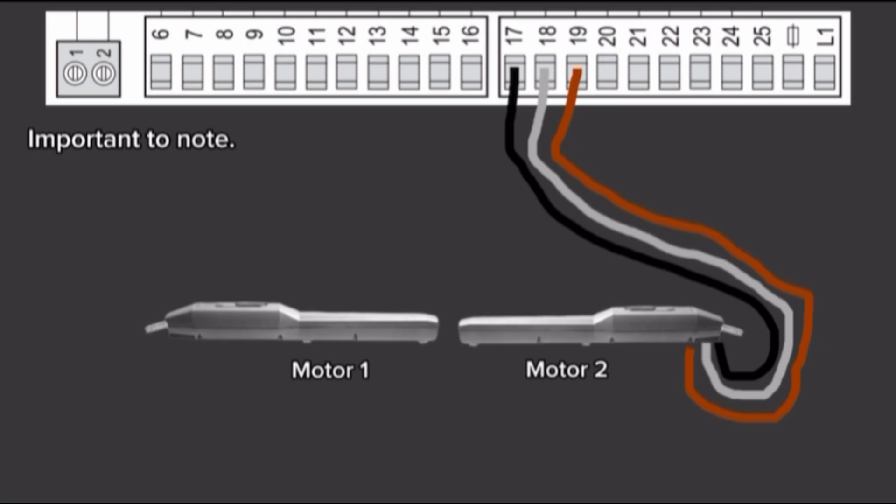Important to Note. Capacitor always connects between phase wires. Don't connect with motor common. Let's connect Capacitor for Motor 2 Phase Wire.